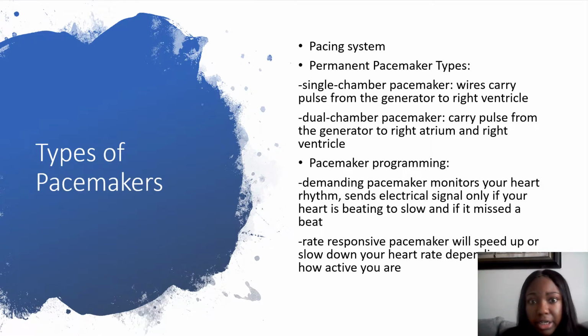And then you have permanent pacemakers. You have single and dual chamber. They both monitor the heart and send out pacing signals as needed to meet the physiological demands. A single chamber pacemaker usually has a lead to carry signals to and from the right atrium or right ventricle, and is usually used for individuals whose SA node sends out signals too slowly. A dual chamber pacemaker has two leads. The tip of one lead is at the right atrium, and the tip of the other is at the right ventricle. This type of pacemaker can monitor and deliver impulses to either or both of the heart chambers. This type is used when the conduction pathway is completely blocked.